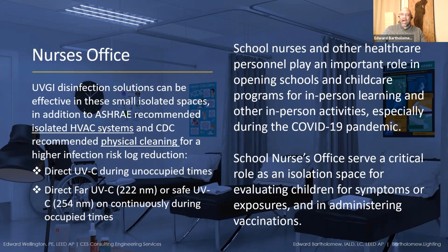You could also do it during occupied times with a continuous either 222 nanometer far UVC or an effective 254 nanometer that does not reach the threshold of being an eye or skin irritant.